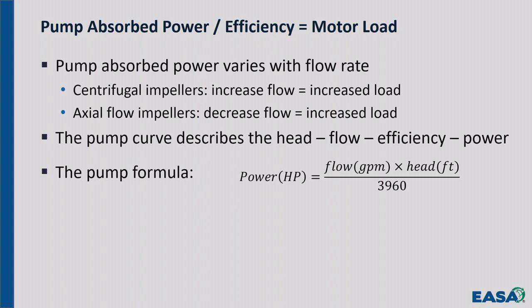Okay? If you're international and you're using kilowatts and cubic meters per hour and meters of head, the 3960 changes to a different number. But other than that, flow times head, adjusted by a constant just to take care of the units, equals power. It's that simple. Flow times head equals power. You should understand that. If you understand that and you know that your motor is pulling high current and you're pretty sure there's nothing wrong with the motor, guess where the problem really is? Something is wrong with your head and your flow, and you're pulling too much power.